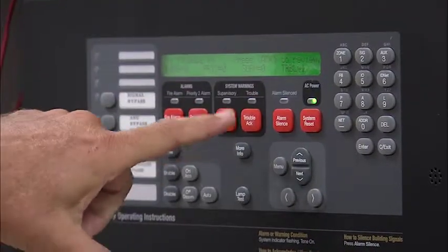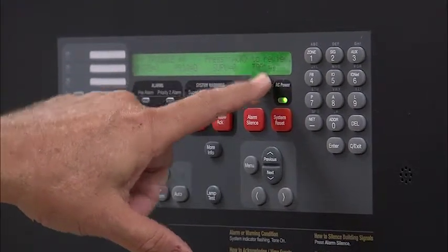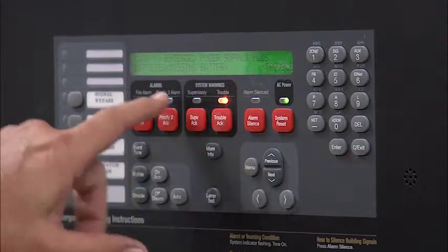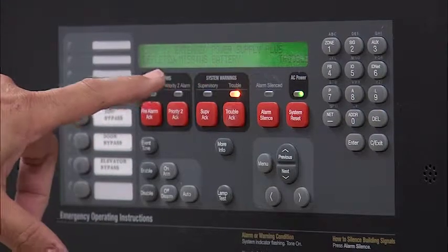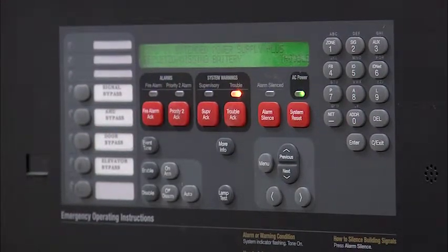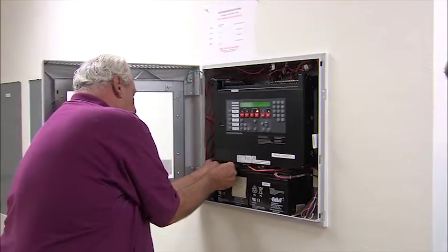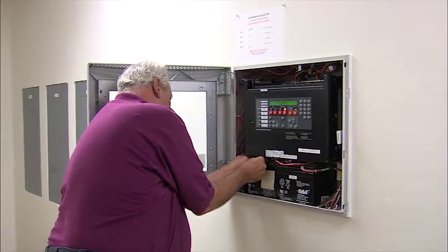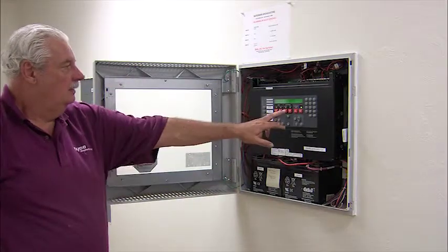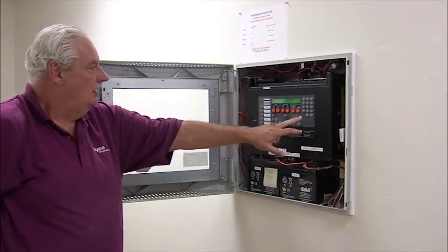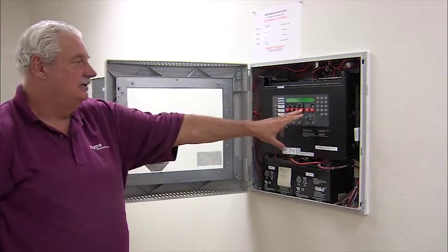Okay, what's going to happen? You're going to get a trouble light flashing. It's going to tell you the number of troubles that there are on the panel, right here, 1. Press the acknowledge. It's going to tell you extended power supply, depleted or missing battery. Okay, so that's actually the trouble. So that will clear by itself. It doesn't have to be reset. Okay, it's already clear. Okay, so that is the most common thing you're going to do on here, silence the trouble.